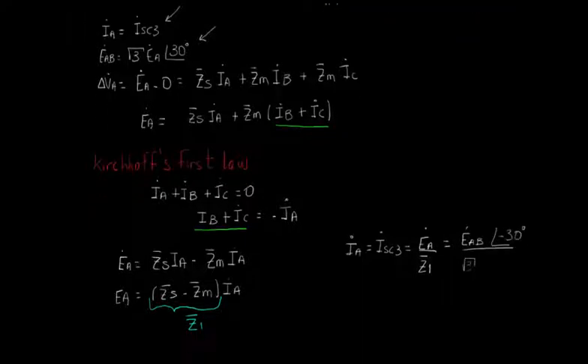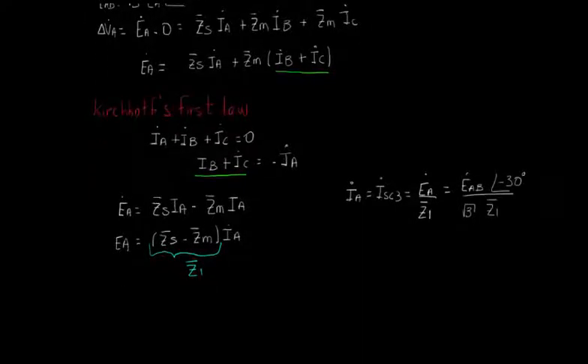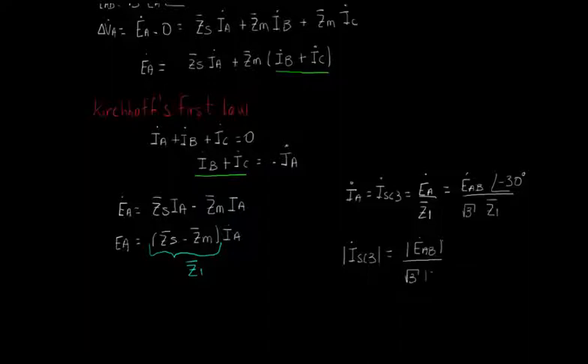Finally, we can write that the three-phase short-circuit current is equal to EA divided by Z1. And writing EA as function of the line-to-line voltage EAB, we can say that the module of ISC3 is equal to the module of EAB divided by square root of 3 times the module of Z1.